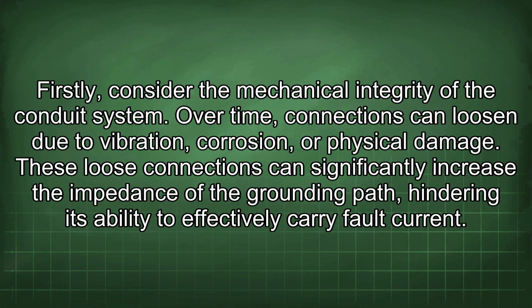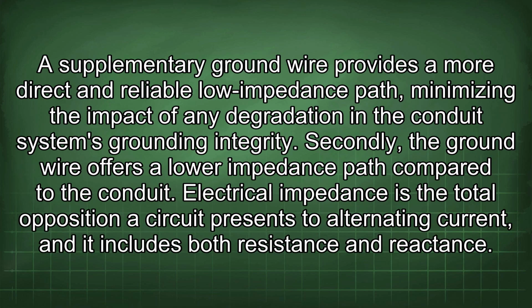Firstly, consider the mechanical integrity of the conduit system. Over time, connections can loosen due to vibration, corrosion, or physical damage. These loose connections can significantly increase the impedance of the grounding path, hindering its ability to effectively carry fault current. A supplementary ground wire provides a more direct and reliable low-impedance path, minimizing the impact of any degradation in the conduit system's grounding integrity.